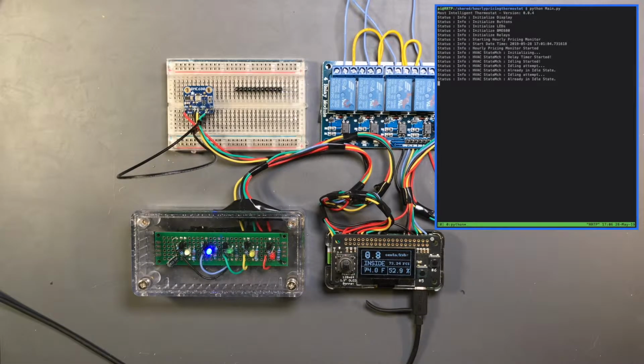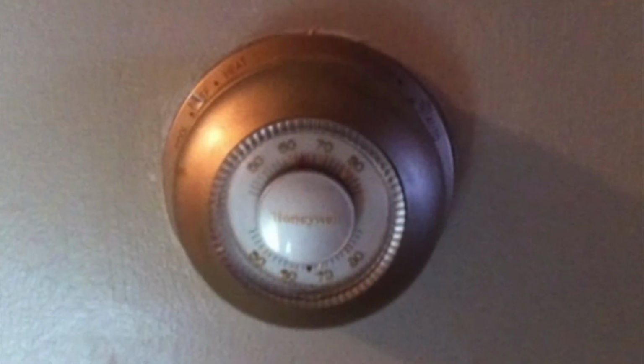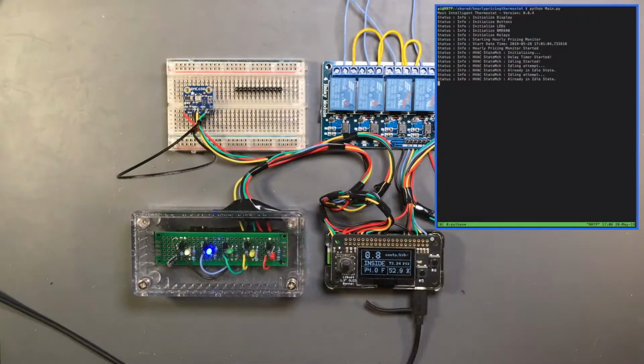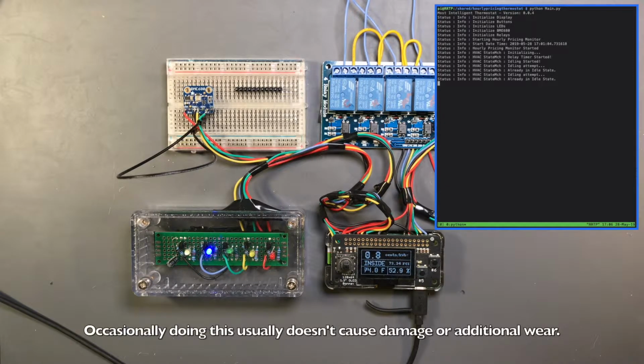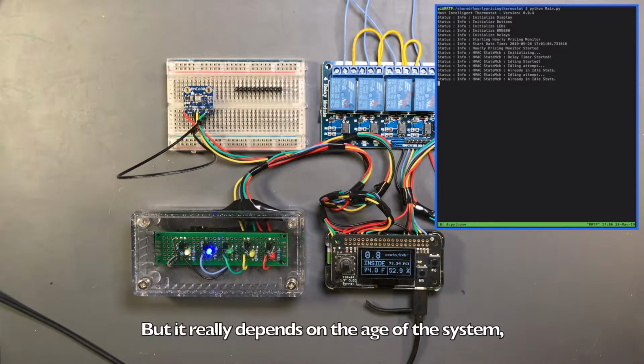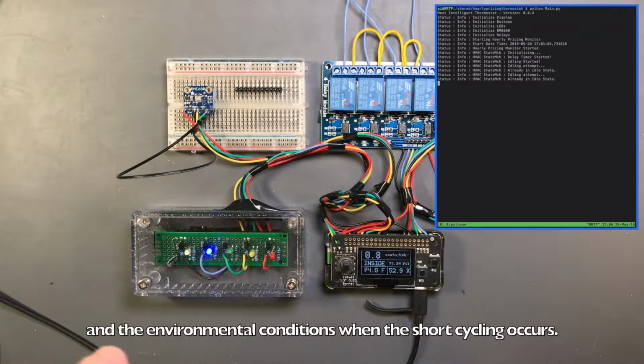And so you might notice that if you ever short cycled your air conditioner, turned it off and back on again with an old analog turny thermostat, you might see all your lights dim a little bit more than usual. Or if you're close to the air conditioner, you might hear it make a quite nasty sounding noise. Digital thermostats have a 4 or 5 minute delay to prevent that, to allow the pressure to bleed off.